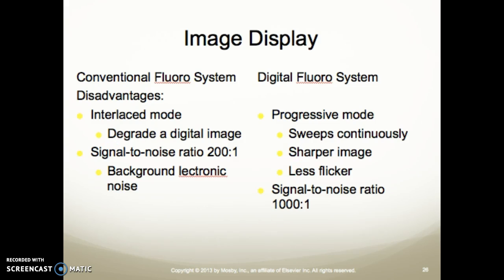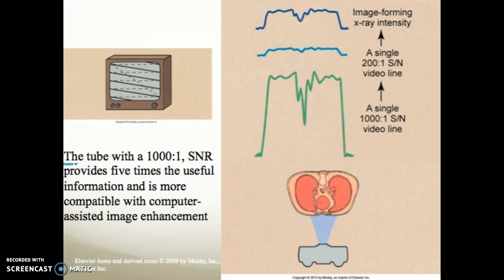Comparing image display: conventional fluoroscopy systems use interlaced modes, which degrade the digital image, and have a signal-to-noise ratio of about 200 to 1, along with background electronic noise. With a digital fluoroscopy system, progressive mode sweeps continuously, providing a sharper image with less flicker and a signal-to-noise ratio of 1000 to 1. The 1000 to 1 SNR provides five times the useful information and is more compatible with computer-assisted image enhancement.